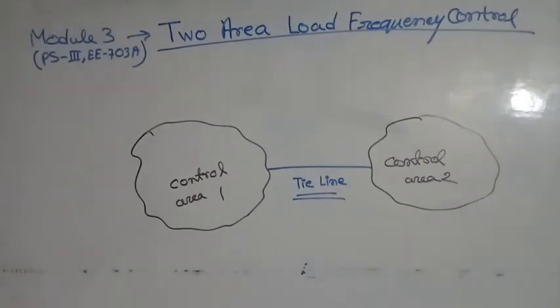The control objective now is to regulate the frequency of each area and to simultaneously regulate the tie line power as per inter-area power contracts. As in the case of frequency, a proportional plus integral controller will be installed so as to give zero steady state error in tie line power flow as compared to the contracted power.